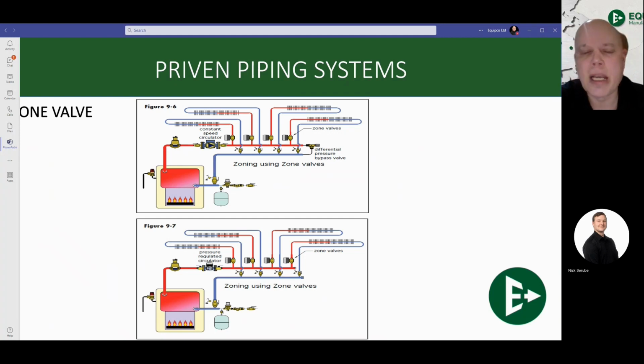If you don't have the differential pressure bypass, all you have is the fixed speed circulator and zone valves. That will lead to what's called the banging zone valve situation, where the zone is going to be closing off against a very high pressure, such as when one zone valve is calling and the rest are closed, and it's going to bang throughout the system. Now, if you've never heard a zone valve bang, it's incredible. It's going to sound like a shotgun is going off inside your house.